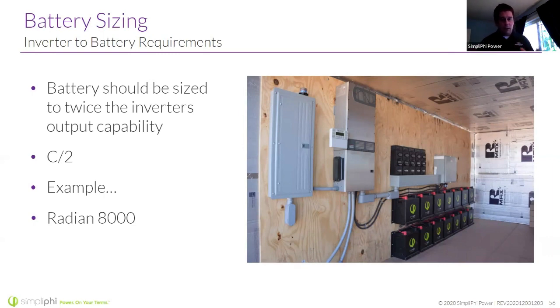of drawing. So you want to do the math and you want to look at that inverter's efficiency rate. So if it's providing 8,000 on the AC side, what does it take from the DC side to get that 8,000 watts? Then you divide that by the maximum discharge rate of the battery. In this example, it's 5 batteries. We can always have one of our sales applications engineers assist you with system design, but it's very important to make sure that you don't set up an inverter that is able to discharge more than your batteries are able to provide.